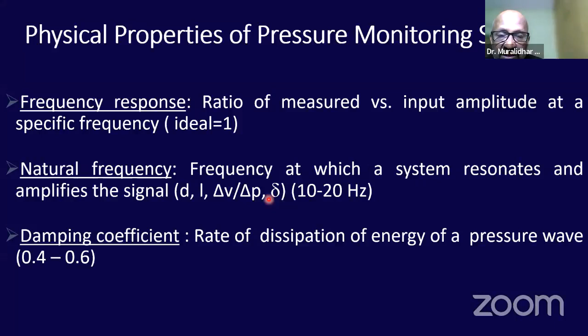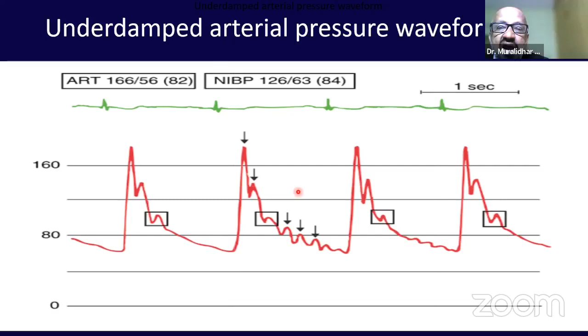The third important principle is called the damping coefficient, which is the rate of dissipation of energy of a pressure waveform, and the normally required damping coefficient in an arterial line system is 0.4 to 0.6. And this tracing shows the underdamped arterial pressure waveform where the systolic peak is increased and diastolic pressure is lowered, and the smaller waves are magnified. But the thing is, the mean arterial pressure will be the same. For example, as is shown in this example, the actual pressure is 120/60 with a mean of 80, but the machine reads 160/55. But as you notice, the mean pressure is similar to the actual pressure.